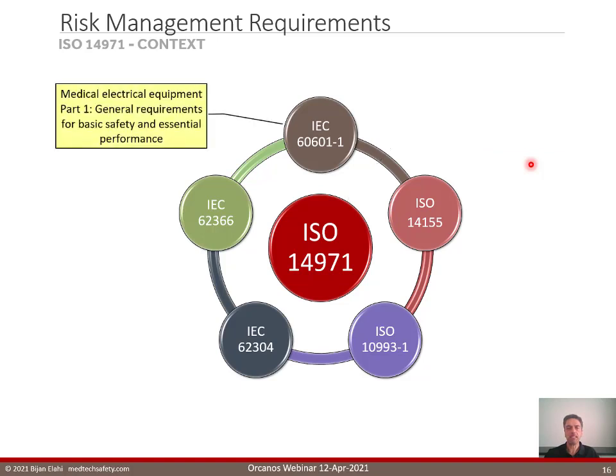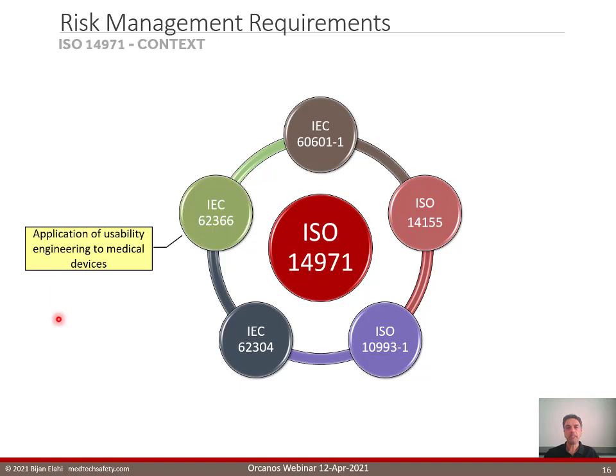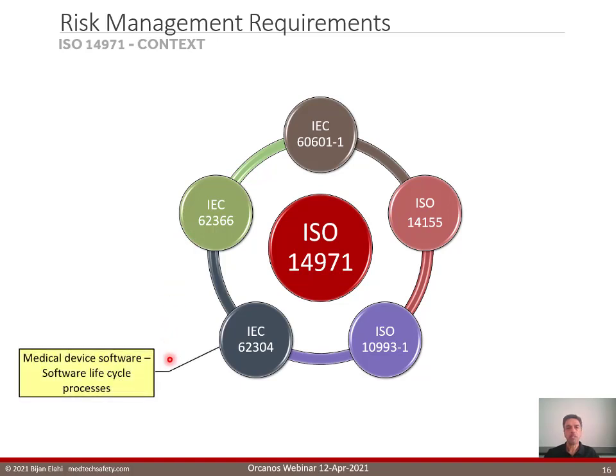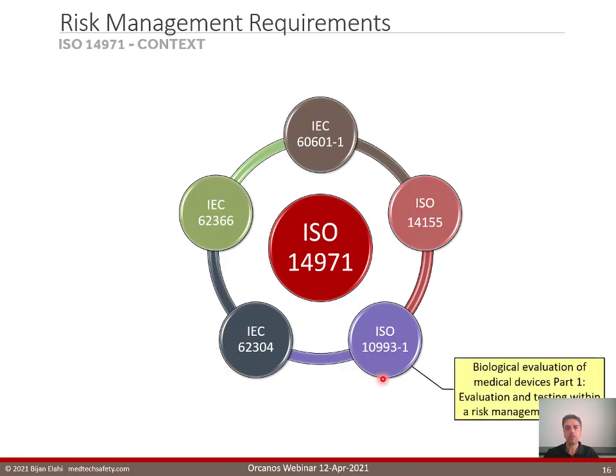If your medical device has electrical properties and is not implantable, then IEC 60601-1, which is a family of standards, references ISO 14971. Almost every medical device has some interface with a human, so it is subject to usability engineering, and therefore you would be subject to IEC 62366. If your medical device has software, then you would be subject to IEC 62304.